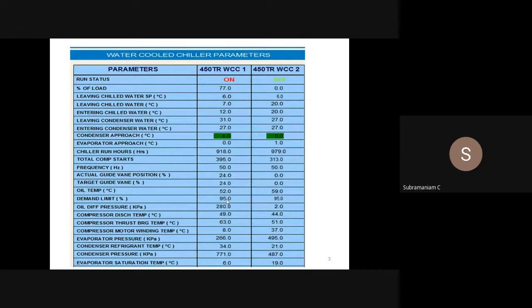Suppose you are having a problem with your transformer and you can't take more than 70% current, we can do current demand limiting set point, so that the chiller will not take more than whatever you are setting. You can set it manually in the touch screen pad of the chiller, or you can set it from BMS also. Compressor thrust bearing temperature. The chiller manufacturer gives all these values. It's all coming there. But we have to have a threshold value for all of this. Some critical things we should put as alarm. If it goes beyond that value, it will give an alarm to the operator.